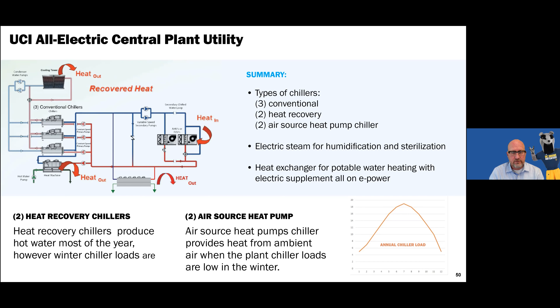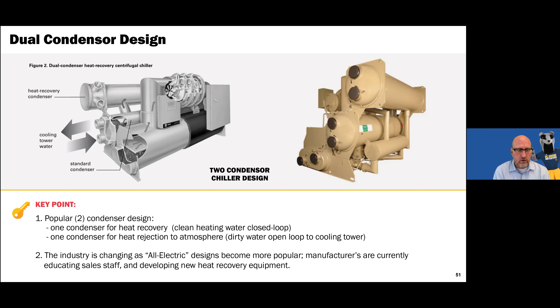So the two condenser chiller design: there's a newer chiller design that has one condenser for cooling tower conventional operation and a second condenser for heat recovery operation. And we're just using this to show that some new equipment designs are becoming available. And, you know, Tom kind of mentioned this earlier, that we feel this project is not only the right place, being in the marsh and in this location for serving clients, but it's the right time in terms of technology and the available equipment to make this all electric design more feasible, more cost effective. Go ahead, Tom.